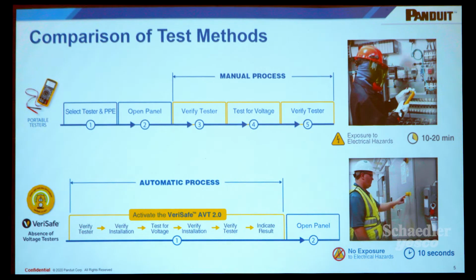It provides the test results. So you don't have to suit up in PPE. You don't have to go find your portable tester. You just walk right up to the panel. The test is done external to the panel. You don't even open the door, right? After you've thrown your disconnect, you hit the button, and it'll give you an indication whether you can service the panel or not.